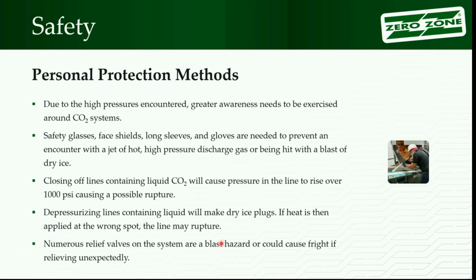So if you had a severe leak right by you and you're getting hit with it, one, it'd be cold and frostbite your skin, and two, it could damage your skin. So that's where, again, think face shields, long sleeves, gloves to prevent that. The story on that, of course: at the case plant, we'd use CO2 to make vapor to look at air curtains and cases. And it's kind of nice because the room doesn't smell like a smoke pen.